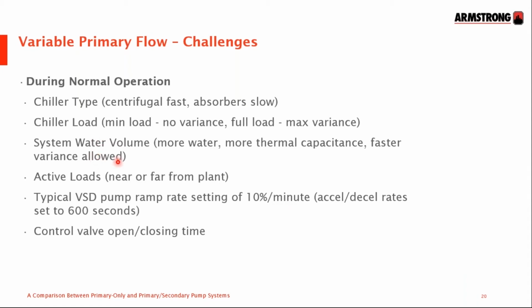The most important of which have very little to do with the chillers themselves. A centrifugal chiller, for example, may handle flow rate changes of 30% per minute in one system, yet in another system it can only handle 5% per minute. Yes, it's the same chiller. The maximum rate of change the chiller can accept depends upon the type of chiller. Centrifugal chillers are relatively fast. Absorption type chillers are very, very slow.